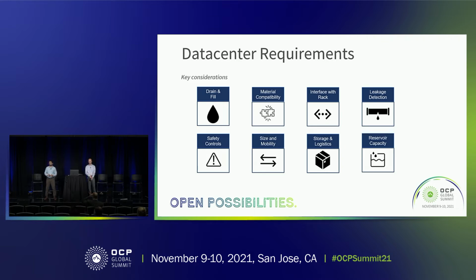Since we are talking about coolants and fluids, it must be ensured that we have the necessary safety controls and leak detection. In the event of a leak, the system should be able to shut itself down completely and alert the user of that leakage.